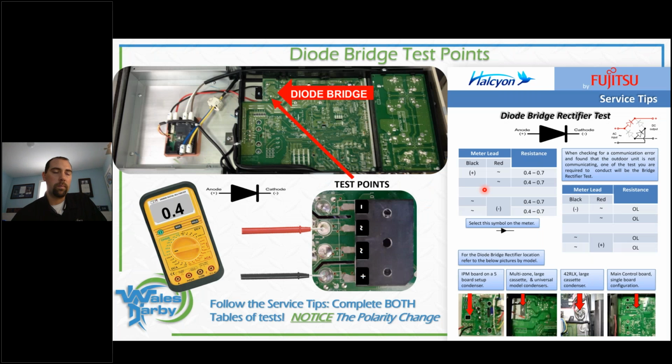So first component, we checked the wires. The wires seem to be good. We got no communication coming out of the outdoor unit. This could be from a power outage. This could be from a couple different things. I'll mention it early here, and we're going to mention it at the end too: it could be a bad grounding system in a home, right?